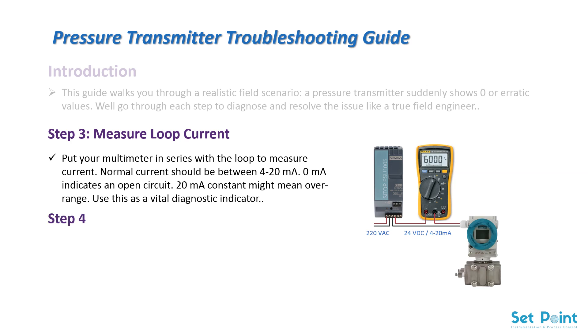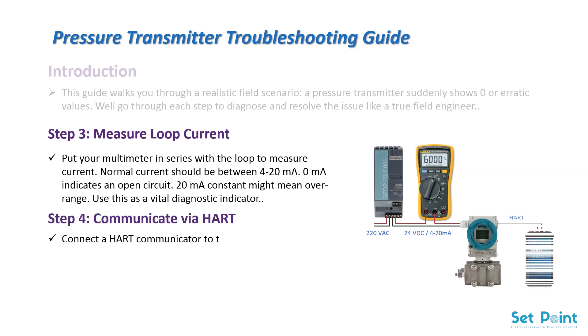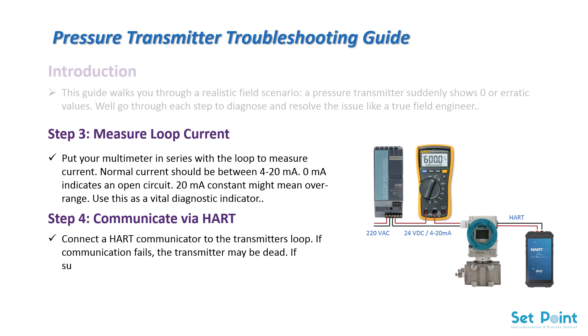Step 4: Communicate via HART. Connect a HART communicator to the transmitter's loop. If communication fails, the transmitter may be dead. If successful, check configuration settings: range, damping, and PV.